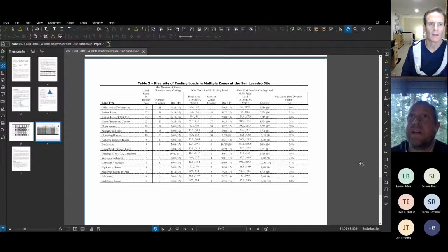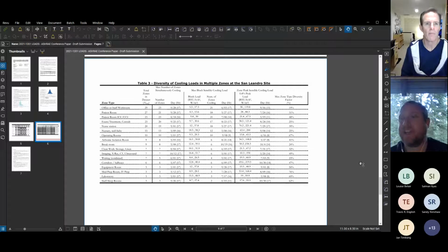I would say it's accurate to what the space is calling for. It's certainly below what the building is providing at that moment. And I think that's the crux of what we're trying to show: the value of being able to do dual temperature or dual resets, or appropriately sizing the upstream system, because there's a ton of cooling capacity happening at the building level that's being reheated back up.